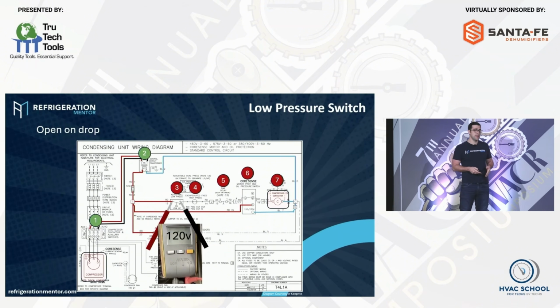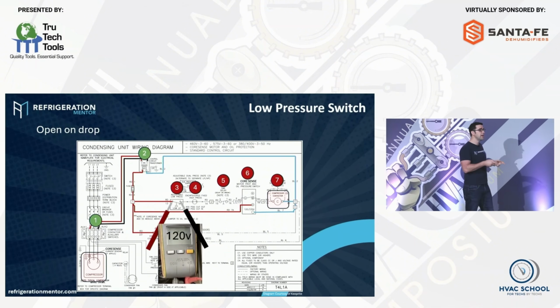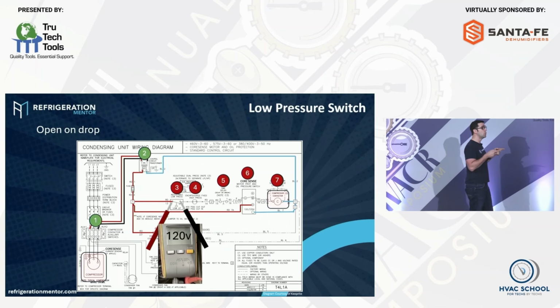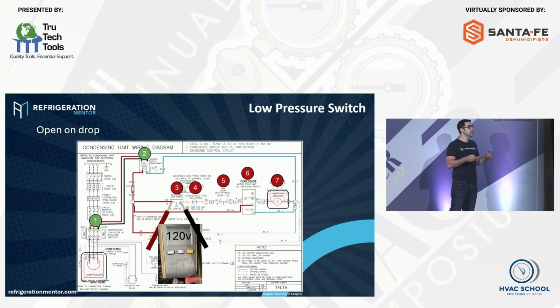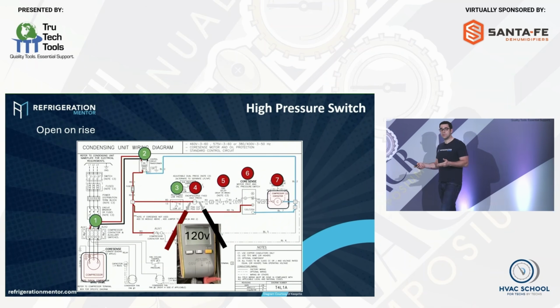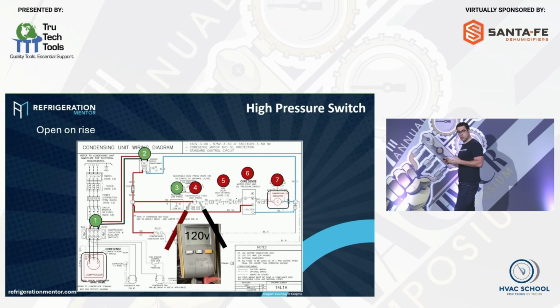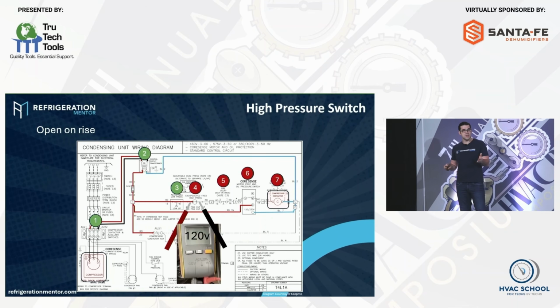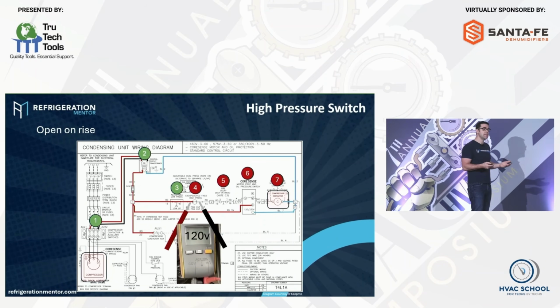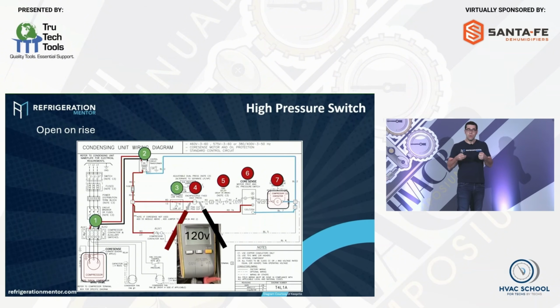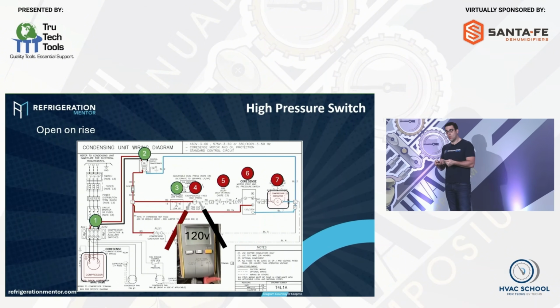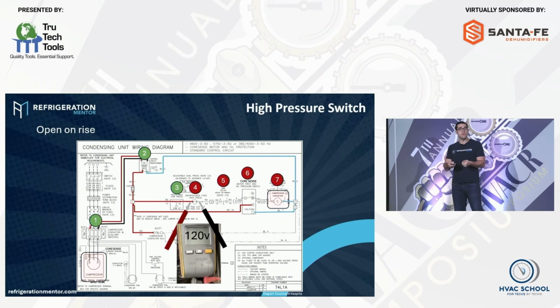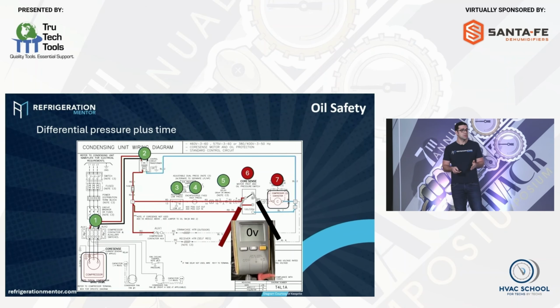Okay, this example is our low pressure switch. If we get 120 volts across the switch, what does that mean? It's open. Okay. Next, the low pressure switch opens on drop. For a high pressure switch, as that pressure rises up, when you hit that certain limit, whatever the set point is, that will open up. So we go across it, we get 120, then that's open. If we get 0, that is closed. This is the way switches work.